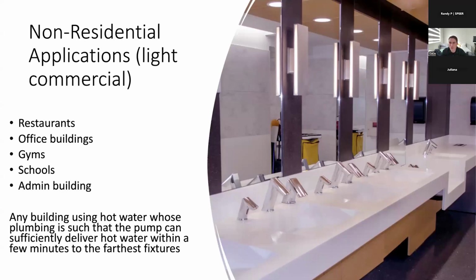So other than residential, there's good application for these types of on-demand systems in what I would call light commercial. So smaller commercial buildings like office buildings or restaurants, or maybe a gym that has a water heater that serves maybe 10 or fewer fixtures in the building, where you can hook up occupancy sensors. So let's take for example a restaurant. They have a very predictable schedule, right? A restaurant may open at 6 a.m. and then close at 10 p.m.